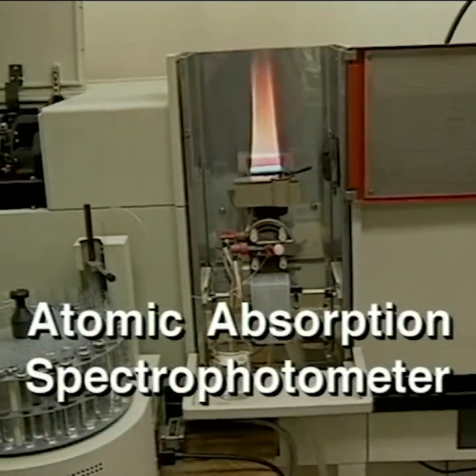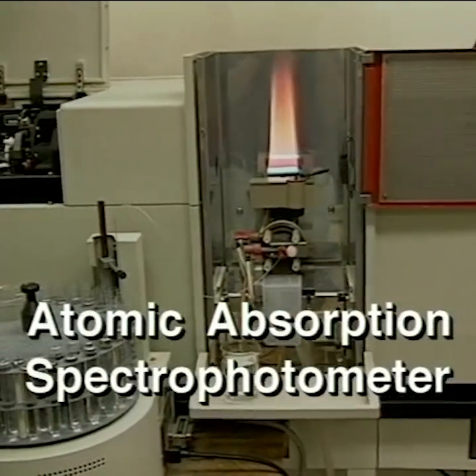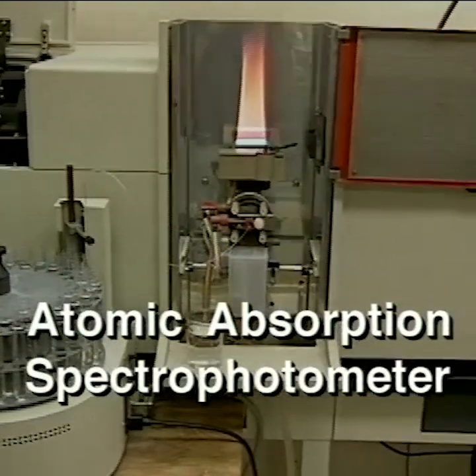Now that we've determined how substances get into the water, it's important to be able to identify them so that we can design the proper equipment for the application. The device to my left is an atomic absorption spectrophotometer. It is utilized to identify the cationic substances in the water, primarily calcium, sodium, iron, and nickel.